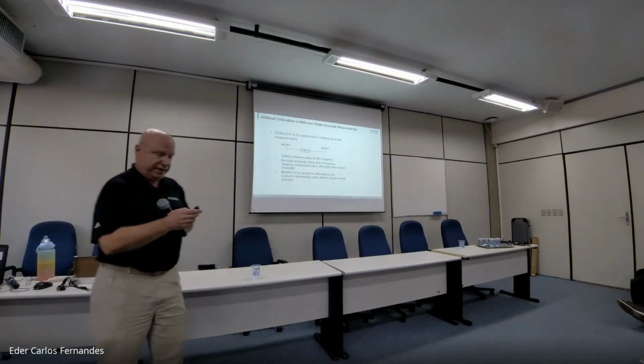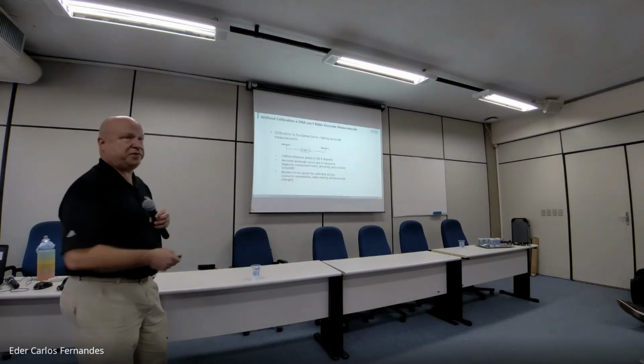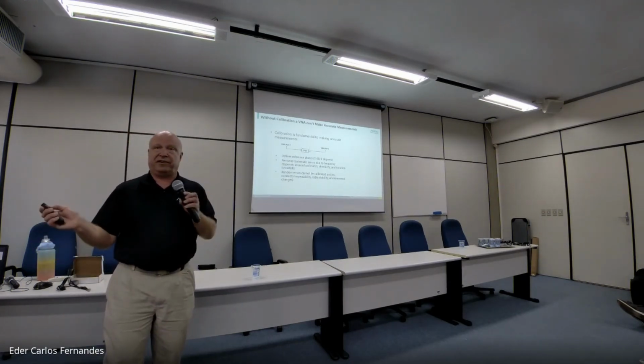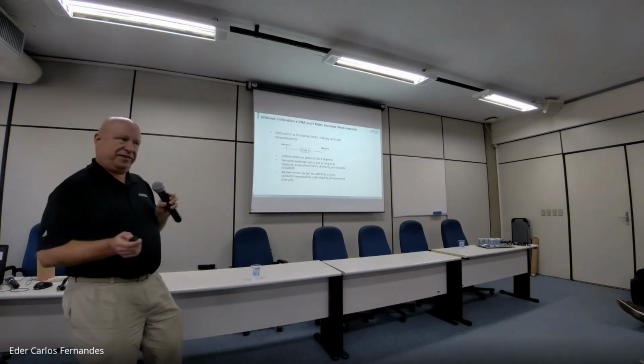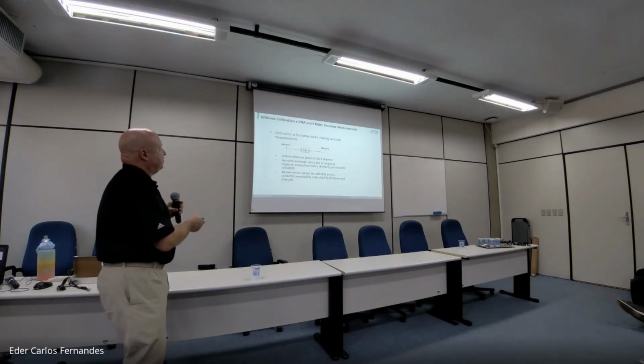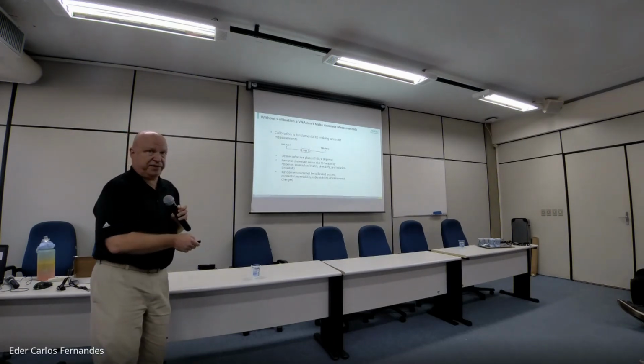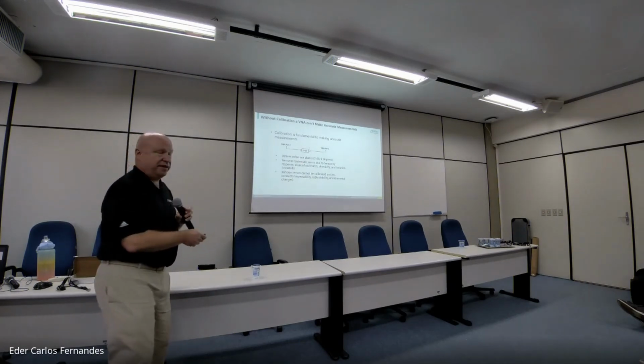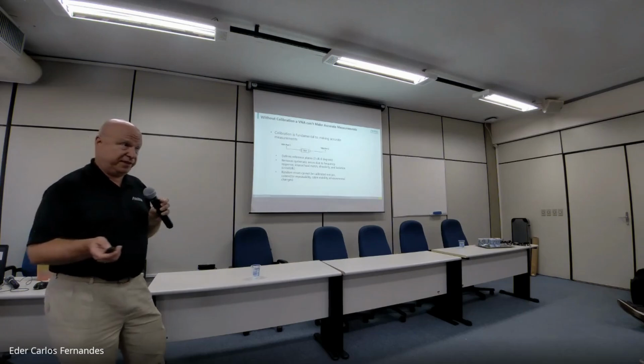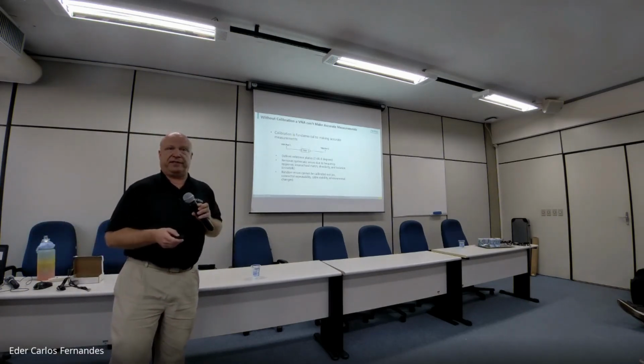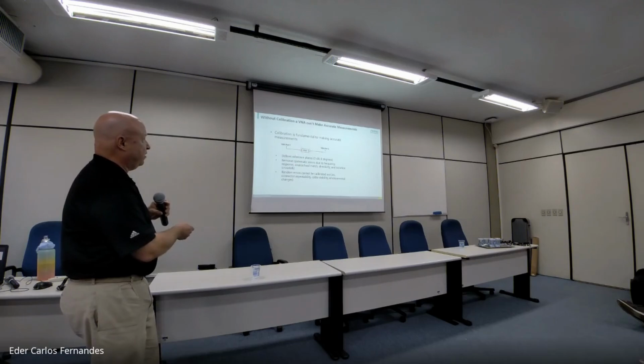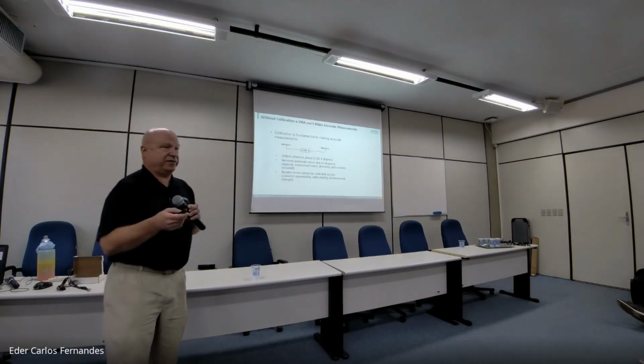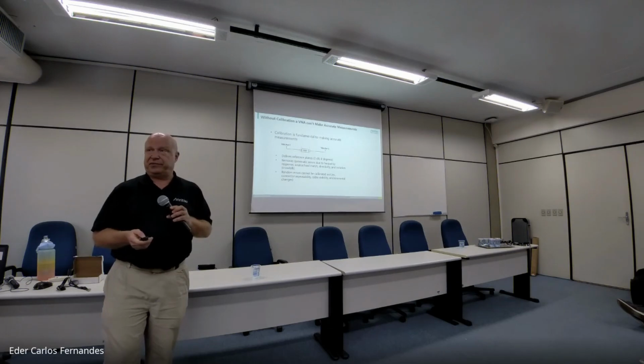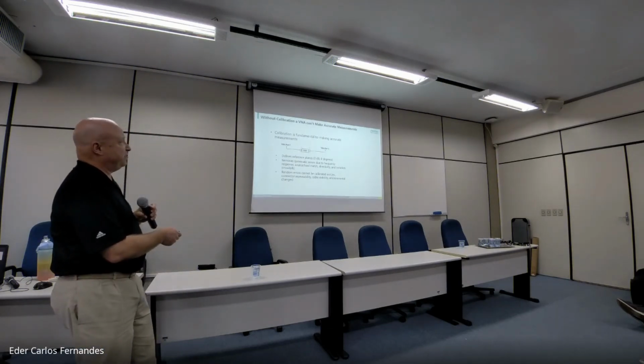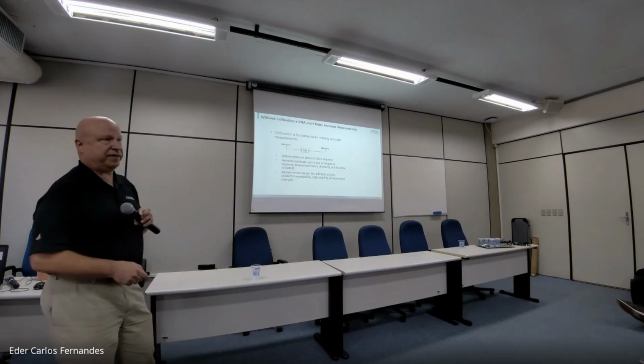All right, calibration, again, as I said, is fundamental to making any accurate measurements with the VNA. Without it, all bets are off. Measurements are raw and not corrected, so they're not accurate. So calibration is essential, and we want to establish where we want our reference plane to be, so that when we measure the device, we don't include these cables or anything else that's non-ideal about the instrument. No instrument is perfect, so that's why we do this. No cable is perfect, so that's why we calibrate, to get all of these other contributors characterized and removed from our measurement system. So at the end, we're measuring between this red dashed line and this red dashed line, and we're only looking at the device that we're interested in.